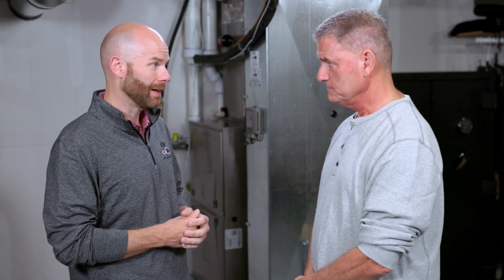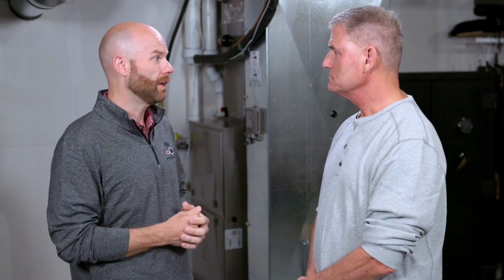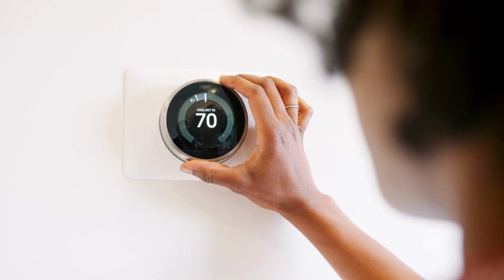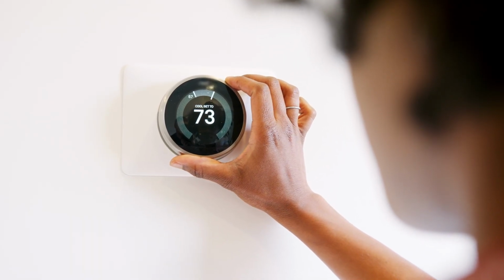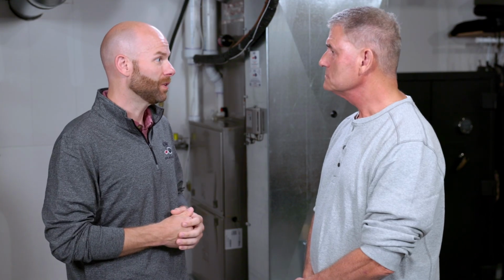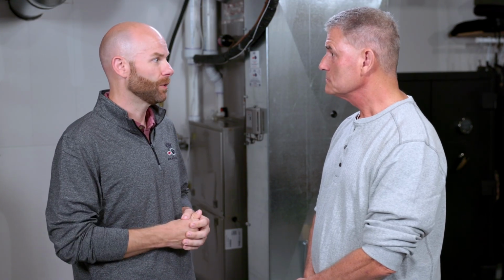Help us understand that setback temperature in terms of efficiency. Daily, Monday through Friday, we go to work, but we can set it back—what's the range you want to shoot for? Typically, if you're gone from the house 6 or 8 hours, 3 to 5 degrees is more than enough. If you're gone overnight, on a day trip, or a long weekend, 10 degrees or more is perfectly fine, so you get that energy savings while you're not home. What we've found is if you set back too far during the day for just a short window, you end up spending so much time recovering that you lose some of the savings you'd have gotten from a smaller setback.